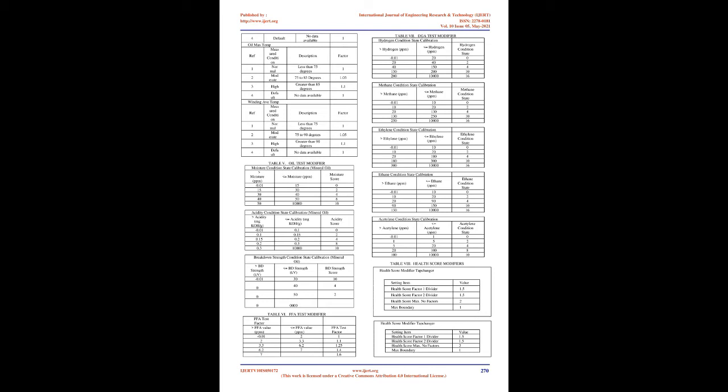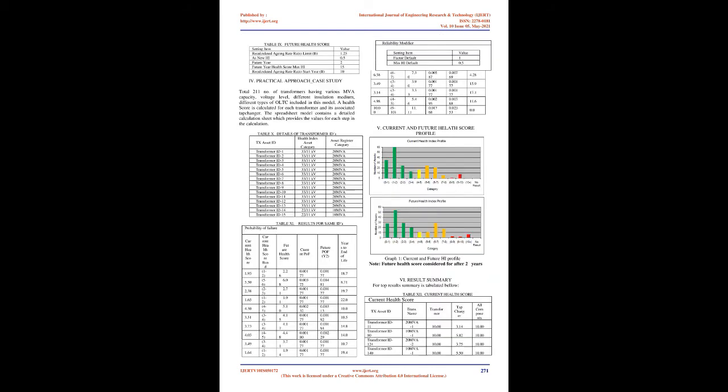This health index calculation technique gives a health score of existing transformers along with probability of failure (POF) and end of life (EOL) data. Developing health index: With the available theoretical data ideal health score is calculated. In actual practice the transformer duty and location factors affect the expected life. Normal theoretical life and expected life are important for calculation of aging rate as ages depend on functional and operational parameters. Initial health score is function of aging rate and defined health score for new asset, i.e. 0.5 as per methodology adopted.